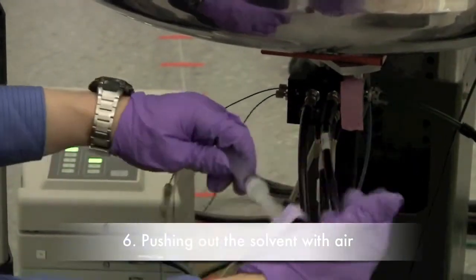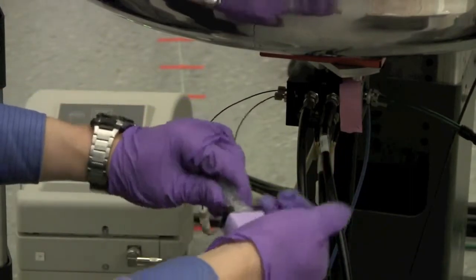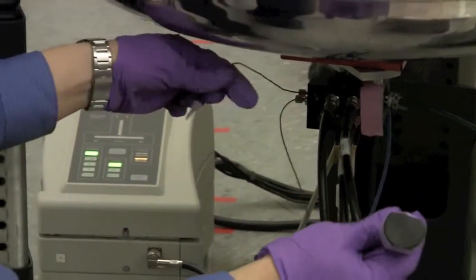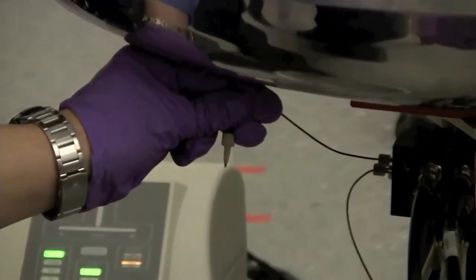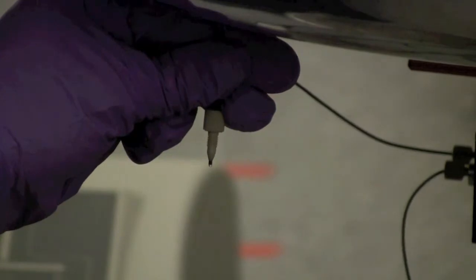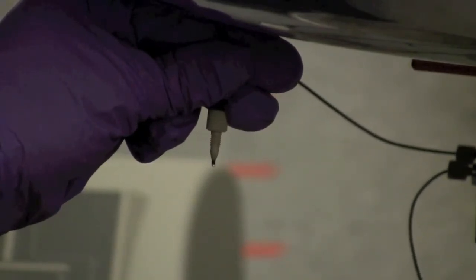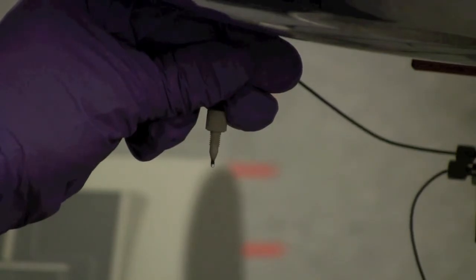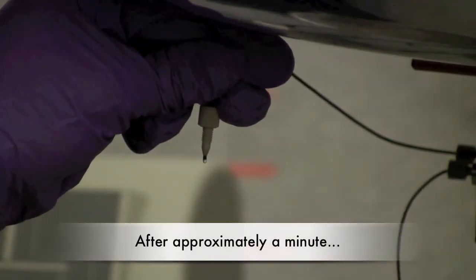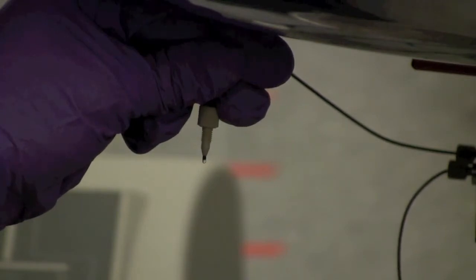And after this, we know that the probe will be pretty clean. So once again, going to wait for the solvent to come out and watch the bubble form on the end of the capillary and wait until the air is pushing it out and there's just air flowing through the capillary. If you hear the lock beeping as this happens, that's a good sign, because that means that you've actually pushed the solvent out of the probe and now the probe has no lock solvent in it and there's nothing for it to lock on, so the lock will beep. That means that it's working and that you're pushing out the solvent.